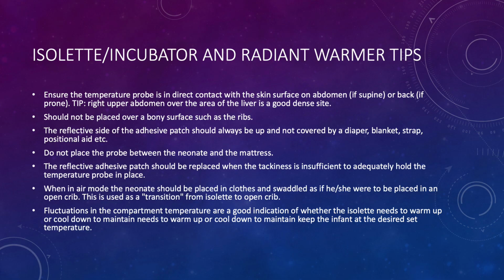The reflective side of the adhesive patch should always be up and not covered by anything like the diaper or any positional aids. Do not place the probe between the neonate and the mattress. The reflective adhesive patch should be replaced when the tackiness is insufficient to hold it in place on the infant's skin. When in air mode, the neonate should be placed in clothes and swaddled.